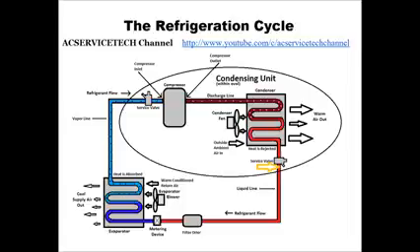The saturated state is where it's transferring most of its energy. The refrigerant is what is carrying the heat and moving it, rejecting it and absorbing it in the refrigerant itself, and most of that energy transfer occurs right in that saturated state. So it comes from the saturated state in the middle of the condenser coil and continues to reject heat as a complete liquid until it comes out of the condenser coil.